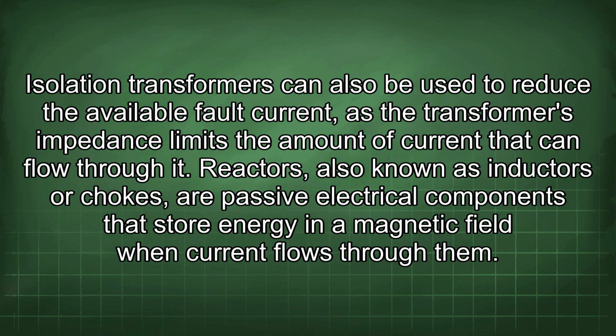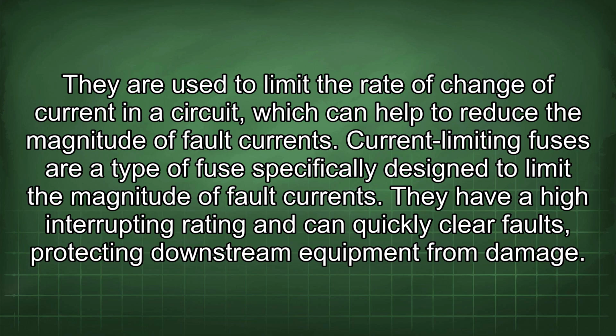Reactors, also known as inductors or chokes, are passive electrical components that store energy in a magnetic field when current flows through them. They are used to limit the rate of change of current in a circuit, which can help to reduce the magnitude of fault currents. Current-limiting fuses are a type of fuse specifically designed to limit the magnitude of fault currents. They have a high interrupting rating and can quickly clear faults, protecting downstream equipment from damage.